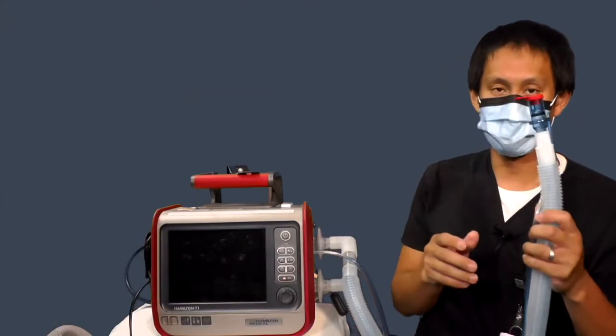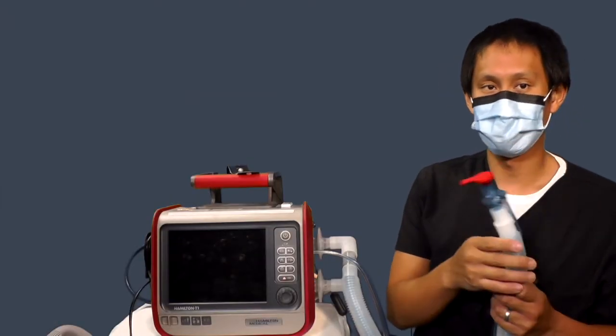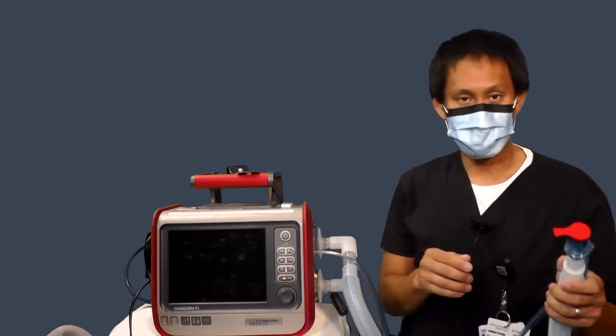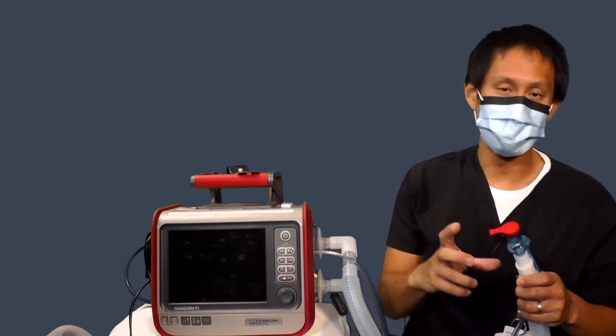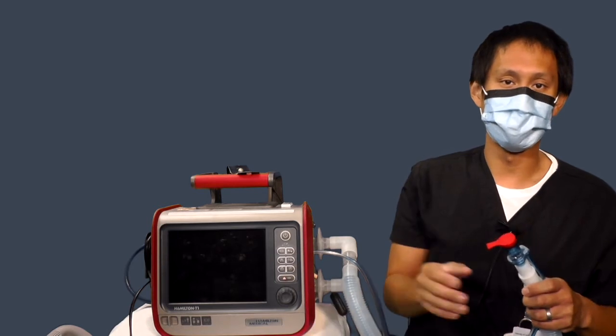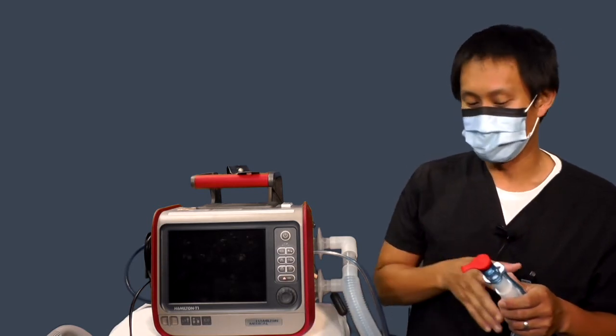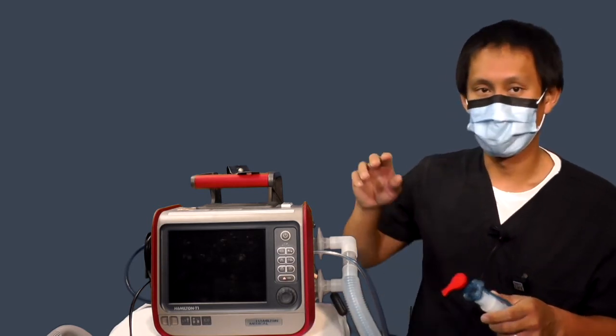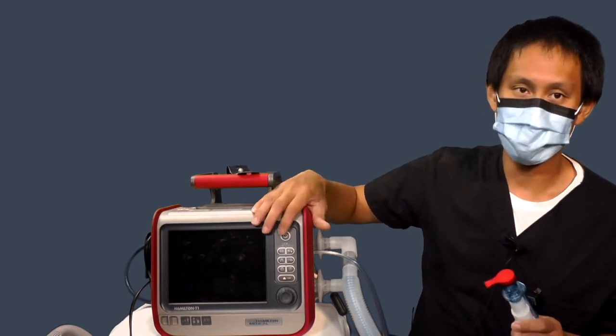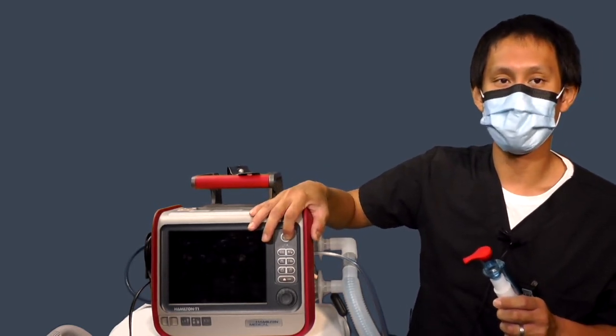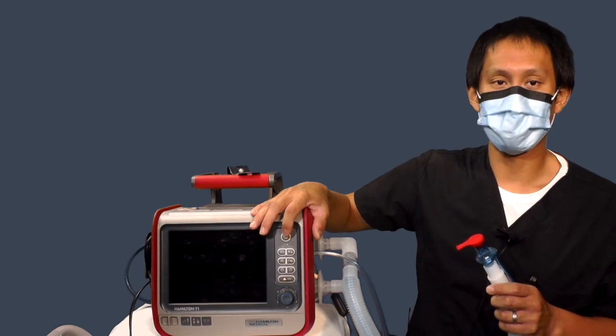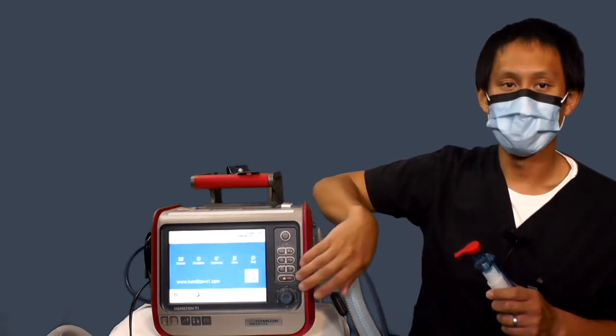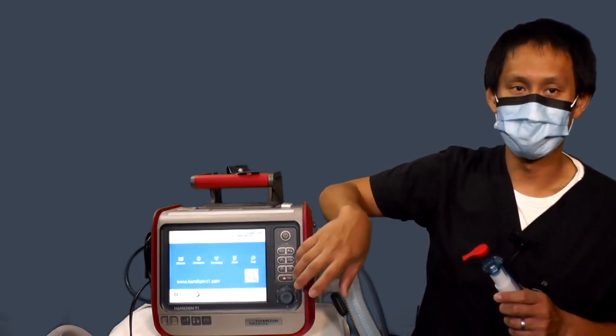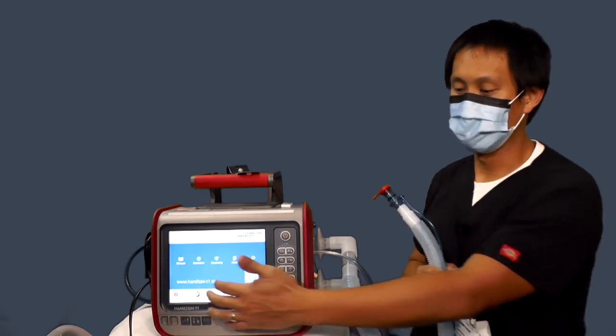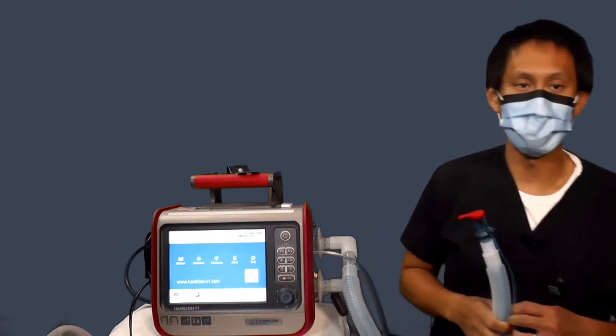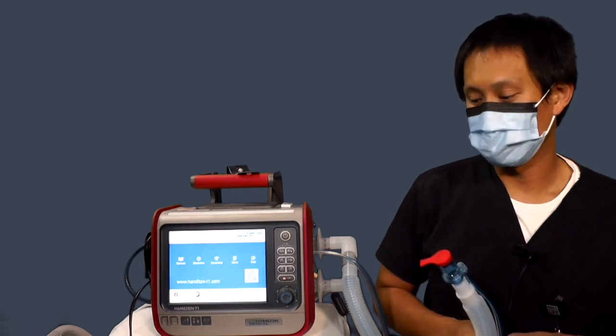For this purpose, I'm just going to use a straight flow sensor and no HME, but like I explained before, you can have it all set up, and when you do the calibration, it'll all account for it. So I'm going to power this up. To power it up, you hit the power button, hold it for 3 seconds, and you'll hear it make some clicking sounds, and that rotary knob will also light up as well. It's doing a self-check right now, and then it'll go to its home screen.